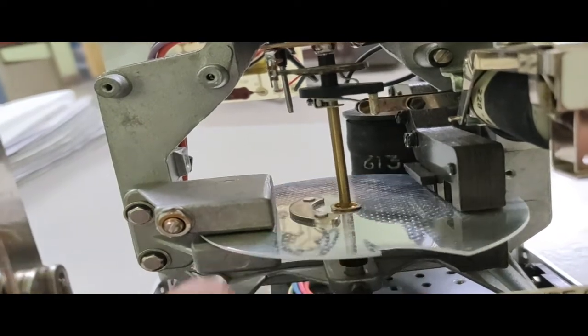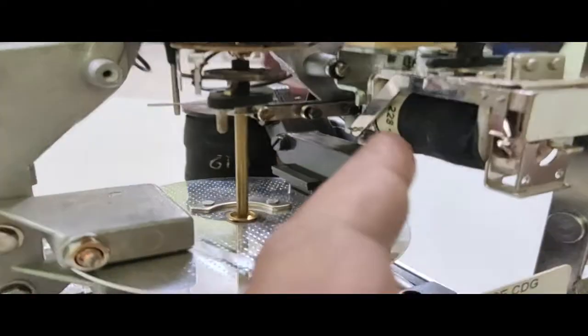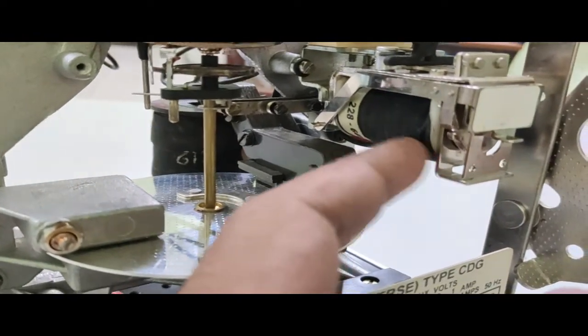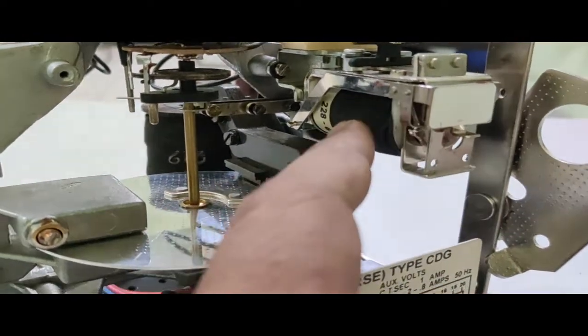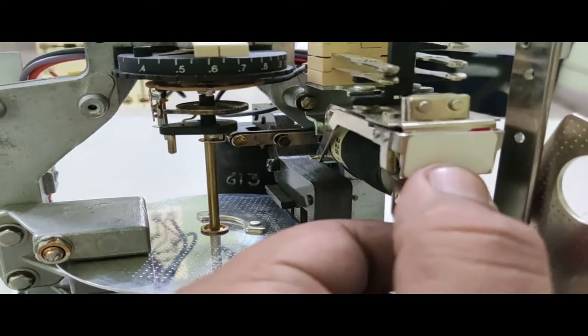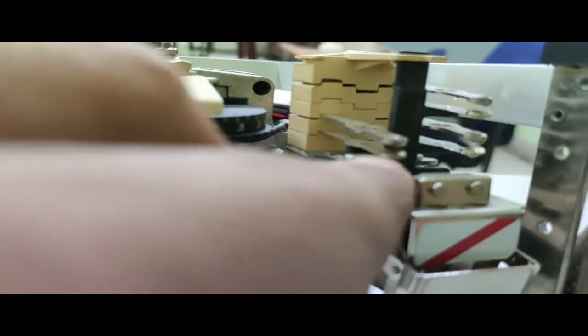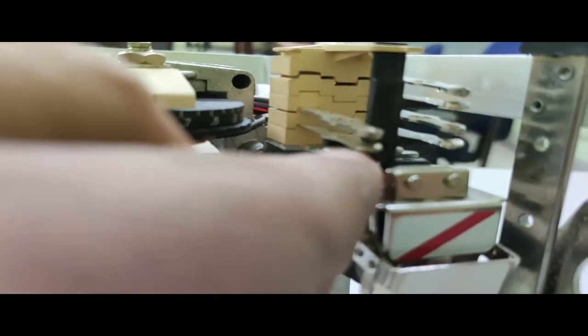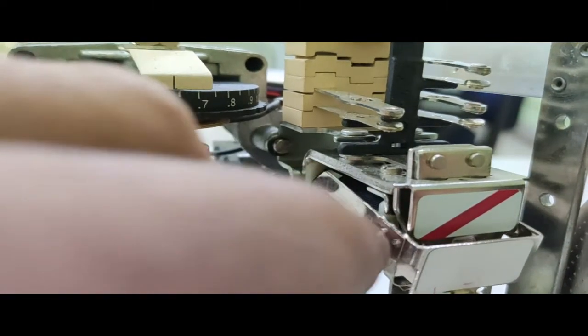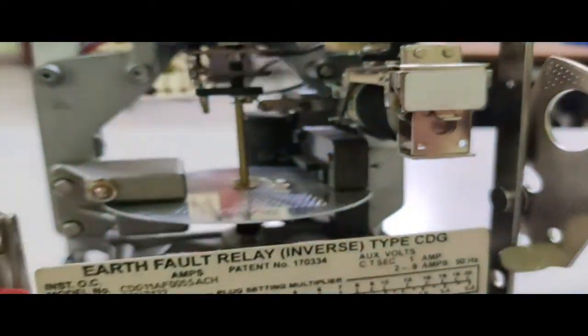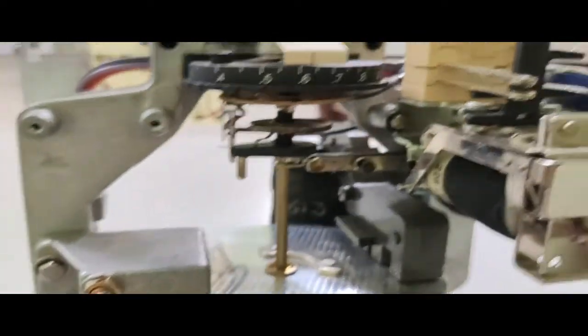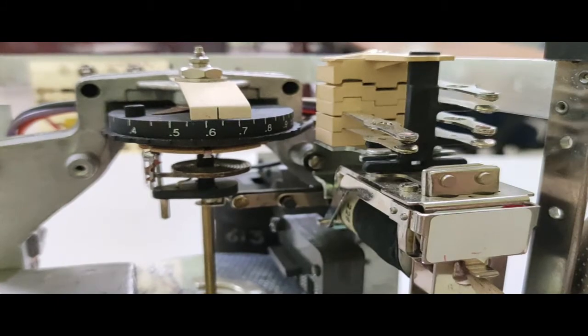So once it becomes closed, the current is able to flow to the tripping coil, and this is nothing but a solenoid type relay. So it attracts the plunger towards it, and when it attracts the plunger, the flag goes down automatically, and this one becomes short circuited. That is also the contacts which are connected to the circuit breaker. Now this one is normally open, but when the solenoid type relay attracts the plunger towards it, this one becomes closed, like this. Or you can see if I push these things like this.